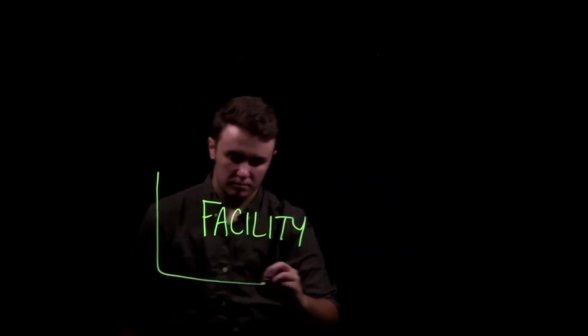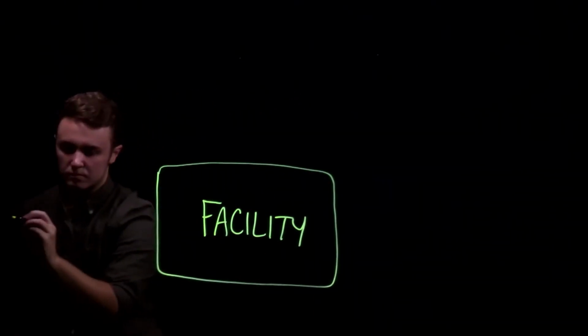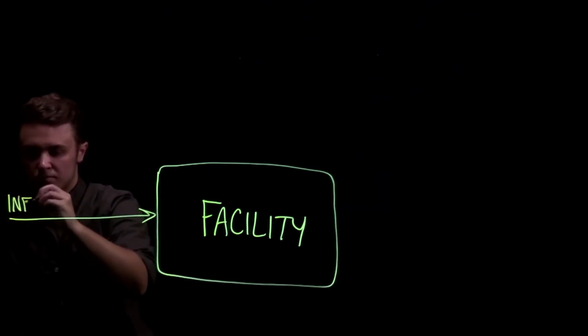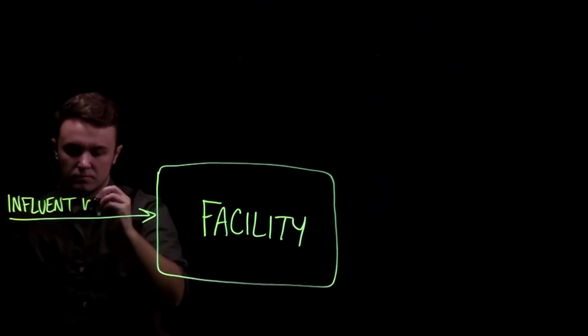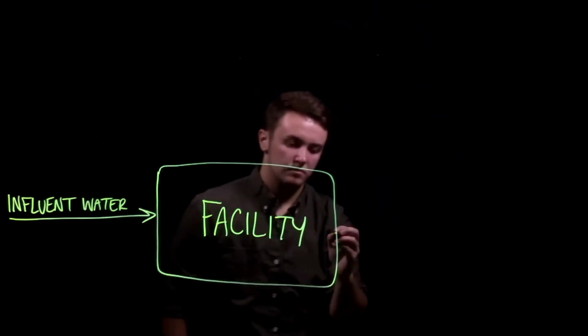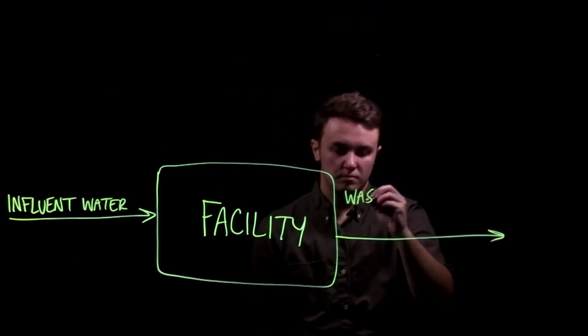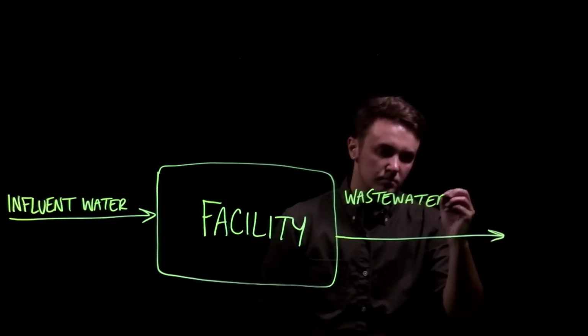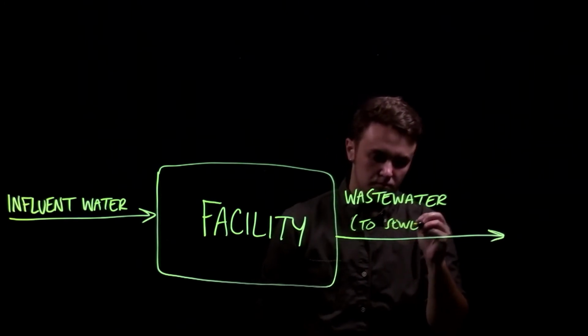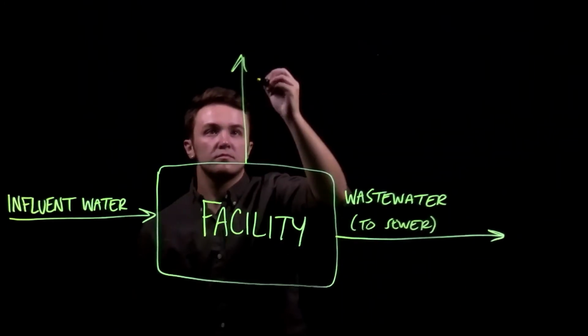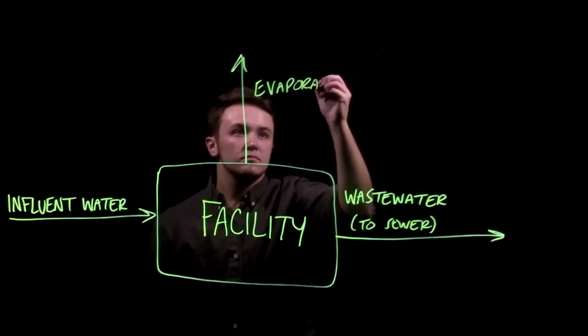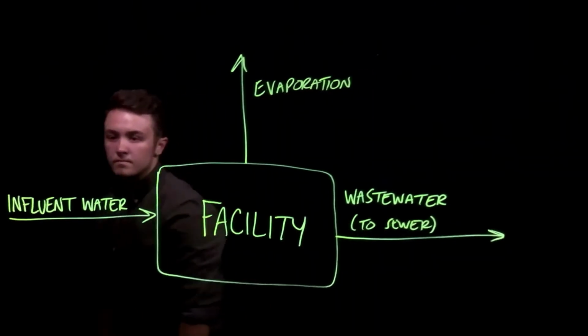The third topic of this video is cooling towers. There are a few ways to optimize cooling towers besides recycling water. Because cooling towers lose a significant amount of water to evaporation, this water is not being treated as wastewater and would be a great opportunity to save on wastewater costs through the use of a deduct meter. Installing a deduct meter for a cooling tower can result in cost savings exceeding $25,000 annually depending on the amount of water metered and the wastewater utility rate.